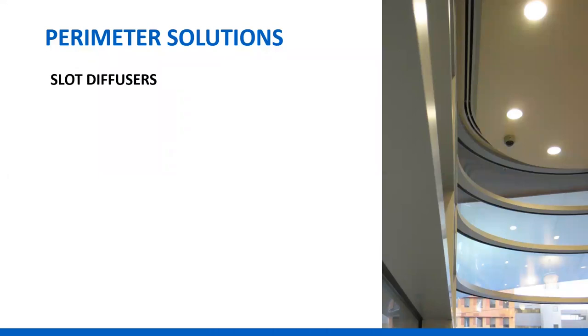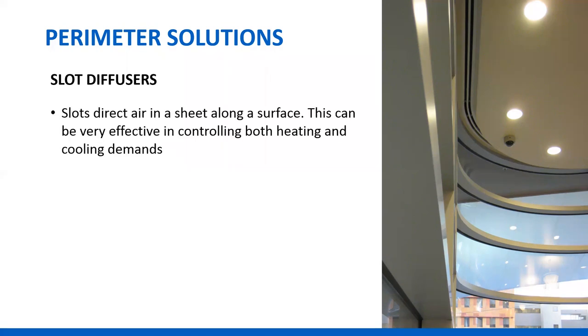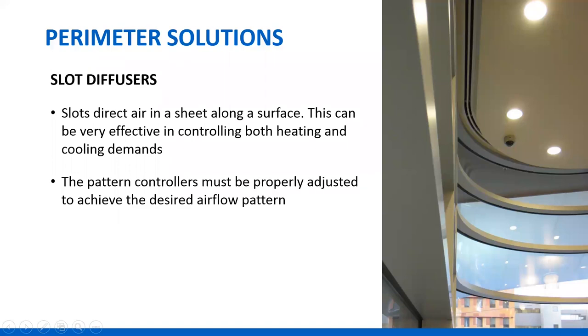Slot diffusers are the most common solution at the perimeter. Linear slot diffusers work best because they direct all the air where you need it — either at the window or into the adjacent perimeter zone. Slots direct air in a sheet, typically along a surface, which has advantages for avoiding inadvertent drop from cold air along the ceiling. However, slot diffusers have to be adjusted. The question comes up: whose job is it to adjust the pattern controller in a linear slot diffuser?